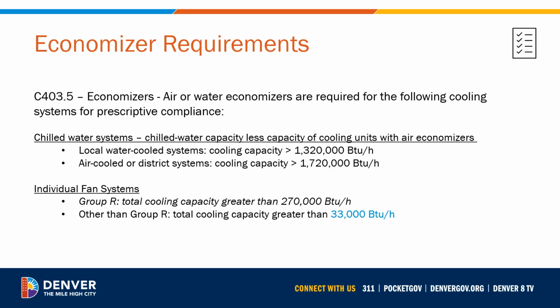Economizers are a prescriptive requirement carried over from the 2019 Denver Energy Code. The requirements for chilled water system economizers have not changed. For individual fan systems, the cooling capacity, which triggers the need for an economizer in buildings other than Group R, has been reduced to 33,000 BTUs per hour. Given that economizers are a prescriptive requirement, a project may pursue a performance compliance pathway for a design without economizers.